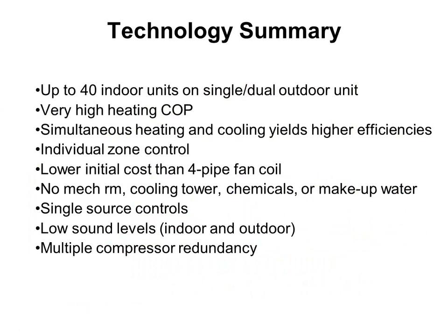All right, so that's kind of the summary of the technology, so we can talk about the energy stuff. You can have lots of indoor units connected to dual or single outdoor units. In some cases, even 3 outdoor units can be manifolded. But you have lots of indoor units connected to one refrigerant network served by one condensing unit system or modules. You get very high heating performance, and we'll talk about that in a minute. You can do simultaneous heating and cooling, right? So I can have one system providing cooling to some zones and heating to other zones, and that does yield very high efficiencies. I can only do the simultaneous when I have the 3-pipe type systems.